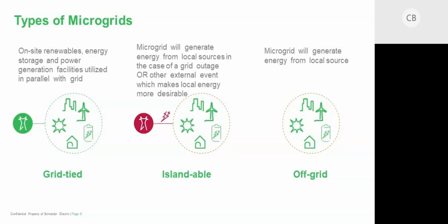And then from mission-critical applications, we understand the island mode. So when we disconnect ourselves from the grid, in the past, this typically happened when the quality of the utility power was not within a tolerable window. We detected this, and then we started the generators, and UPS carried us through. So we were able to island ourselves in this operation, but we did it purely because of the utility power quality, not because of financial metrics or other sustainability aspects. So this is the island mode, where we have the ability to island ourselves off the grid, and then at certain points, come back on the grid.